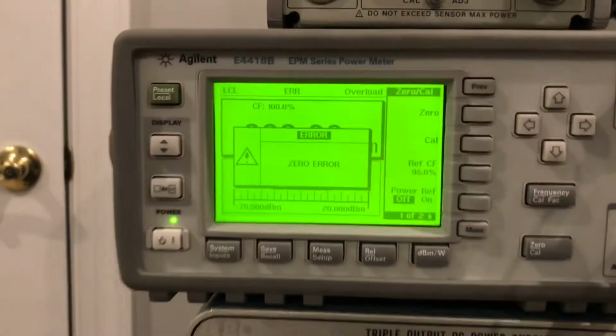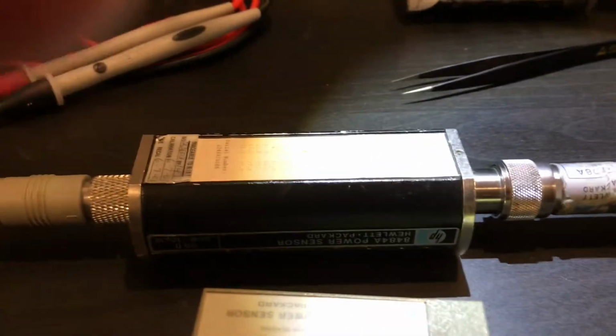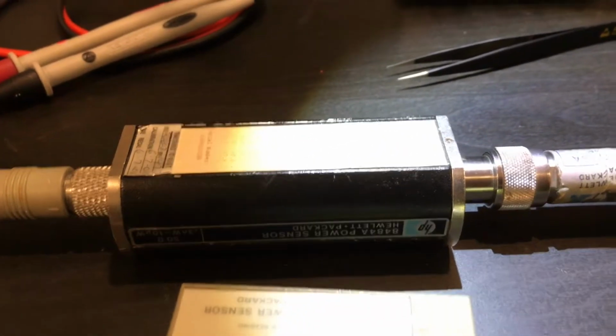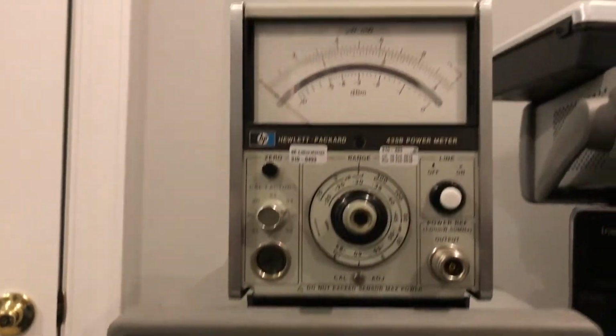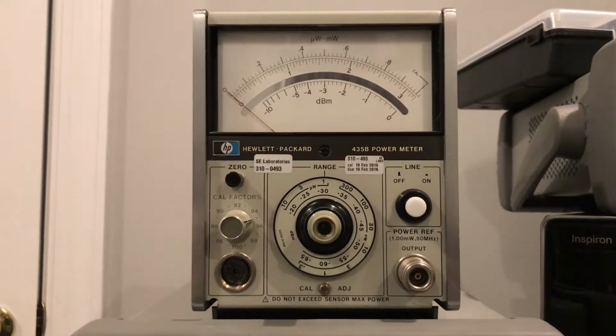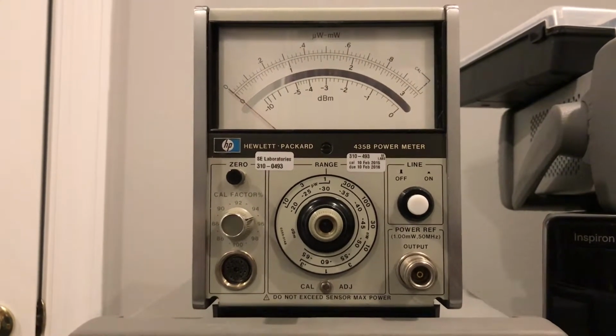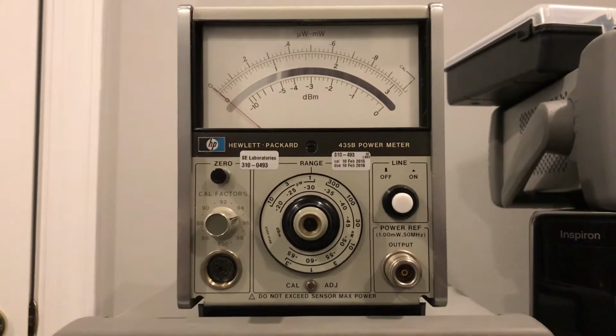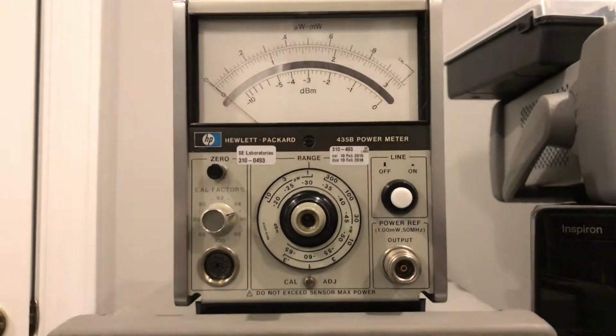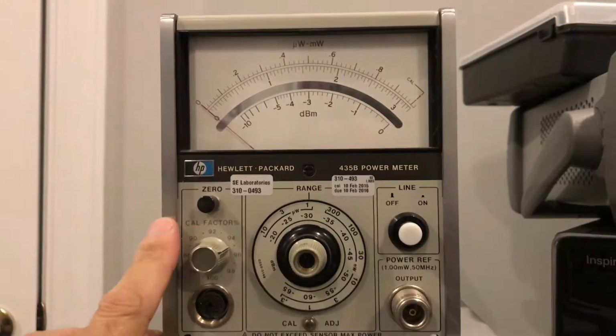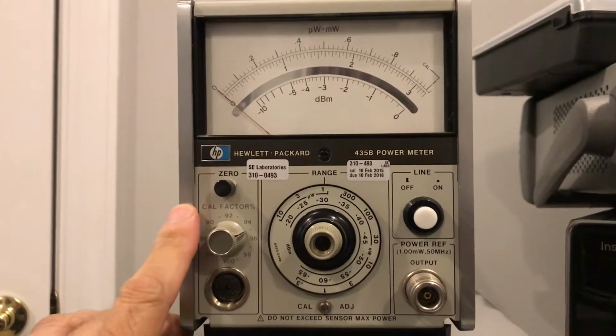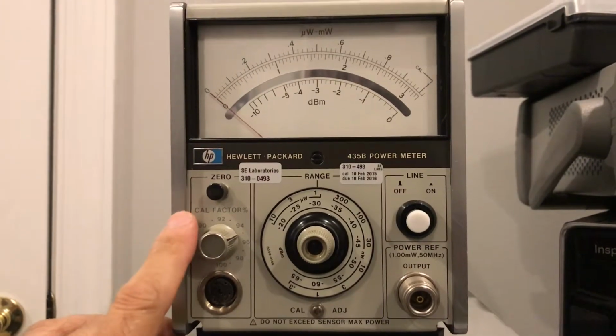And what's going to happen is we get the same error. So we've taken the unit apart, cleaned it out, and it's still showing a 0 error on the instrument. So what I'm going to do now is, you see I've got my HP 435B power meter set up. I'm going to hook this 8484A into this analog power meter, and we're going to zero it on this one. I'm going to show you what I found here.